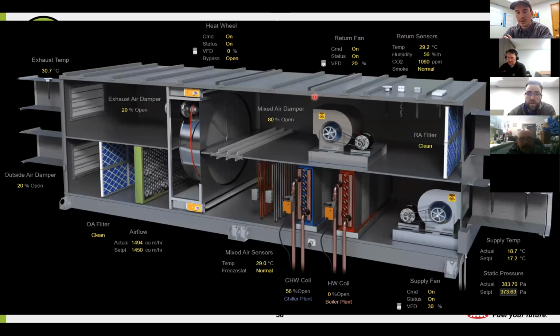Okay. So this is going to be a picture of an air handling unit on a roof, and this is going to tie in basically every single thing we've talked about so far. And I'll kind of just walk through just how the air would go through and what it can do. So when I say it's tying in everything we've talked about so far, I want to point to the fact that we have a chilled water coil here. So there's a chiller on this loop that's supplying chilled water to this one coil that is on this large air handler. This would typically be up on your roof and controlling all the air that's going into the building. It's going to control building pressure. You can see it has CO2 readings on it. So that's demand control ventilation. So we need to see, do we need to bring in more outside air? So yeah, we have a chilled water coil here. So there's a chiller. We have a hot water coil here. So there's a boiler.